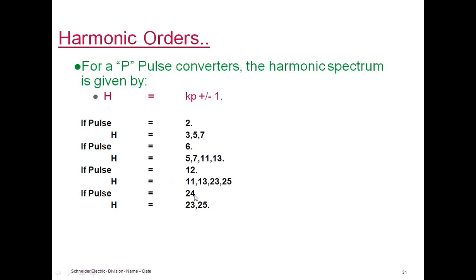The higher the number of pulses, the lower the harmonic spectrum. In other words, one of the ways to solve the harmonic issue is to go for a high number of pulses in the design. For example, in the olden years they used to have 12 pulse and 24 pulse converters for steel applications or cement factory plant applications. That was very expensive, but it worked. Harmonics were reduced drastically.